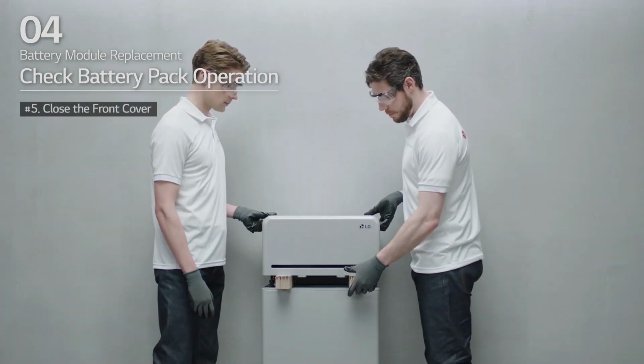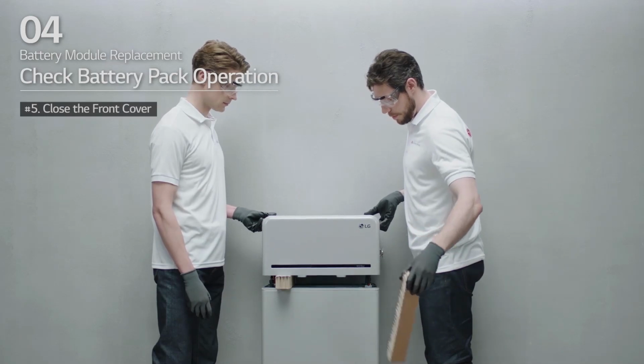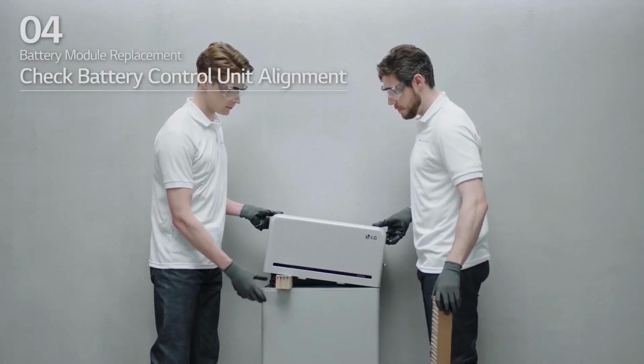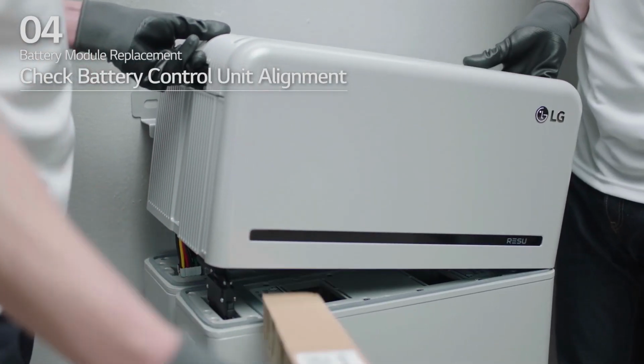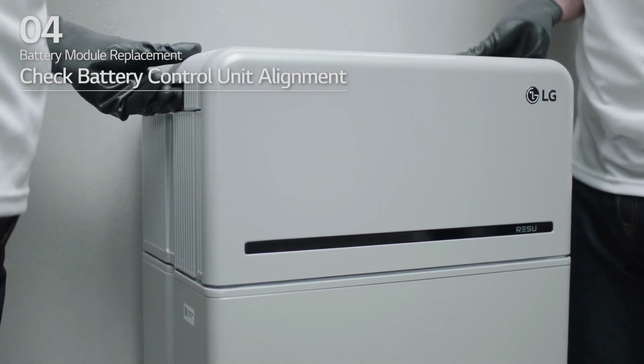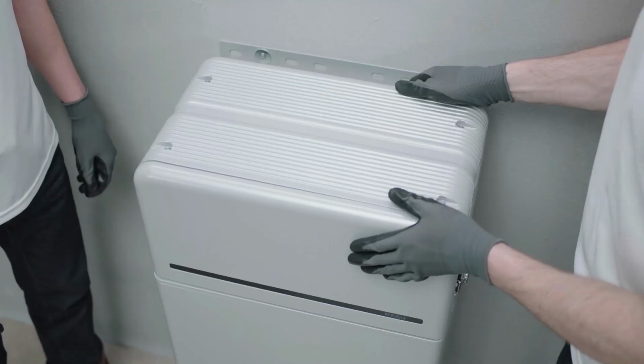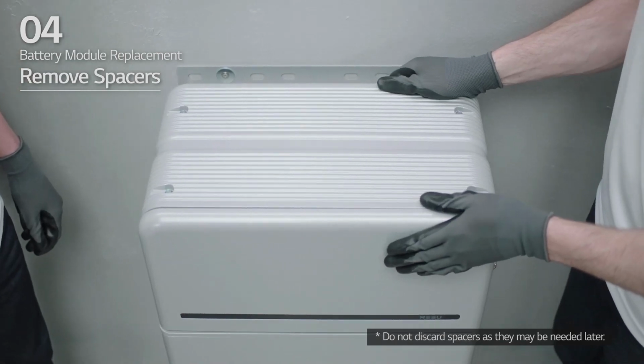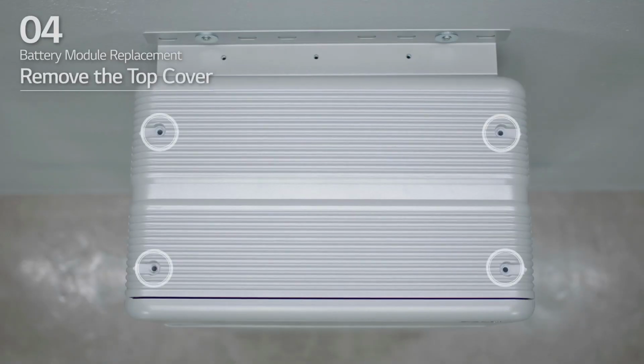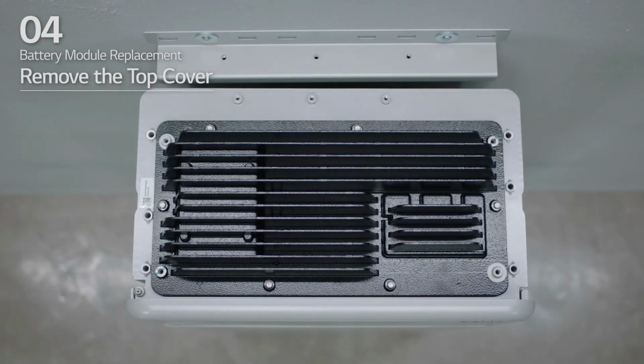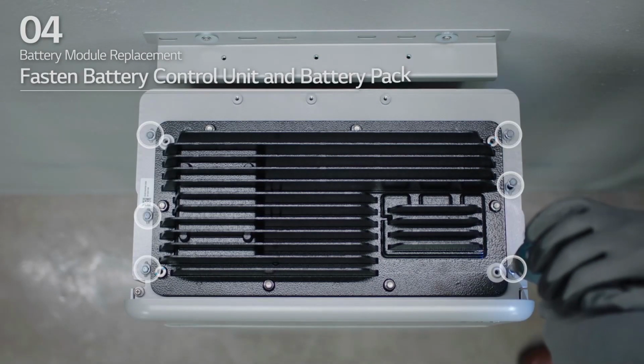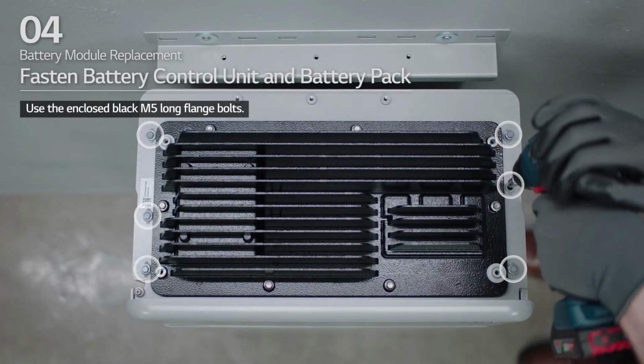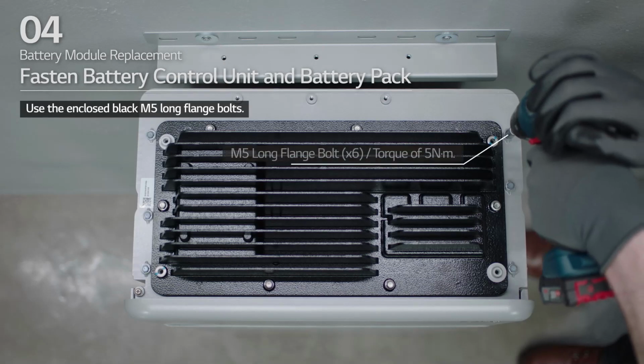Next, check the alignment of the battery control unit. Lift one side of the battery control unit and remove one spacer. Then, do the same on the other side. Realign the battery control unit and loosen the 4 bolts to remove the top cover.